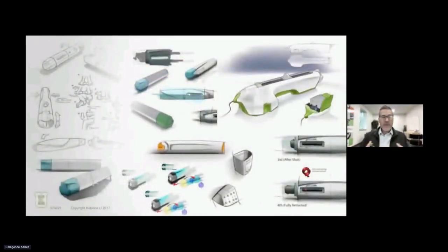So in your design controls, you move further down the development process. Now you get into phase one of your design controls, and you start coming up with concepts, okay? So our human factors engineering process is jiving with our design controls. We get into phase one here, into this ideation phase, and we develop some concepts. So we start with simple concepts, drawings, sketches, 2D schematics, layouts. We show them to users. We talk to users. We have interviews. We get some feedback.